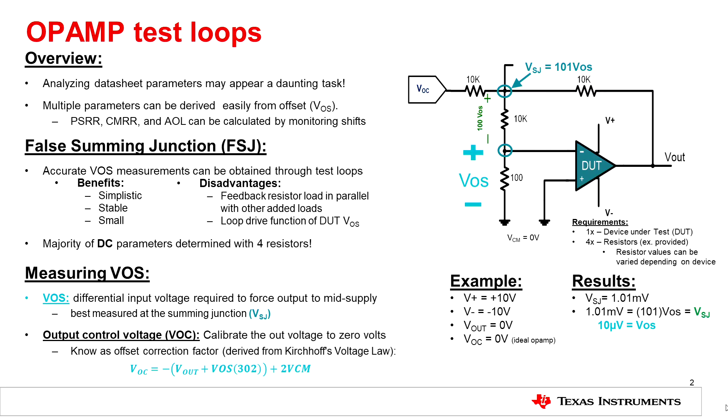The schematic of the false summing junction is provided in the upper right-hand portion of the screen. The false summing junction has various benefits, such as its simplicity and its small form factor. This is mainly due to the reason that there's only four resistors required to measure the majority of DC parameters for an amplifier.